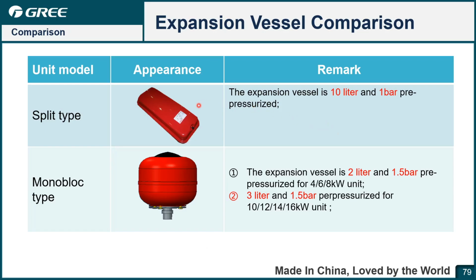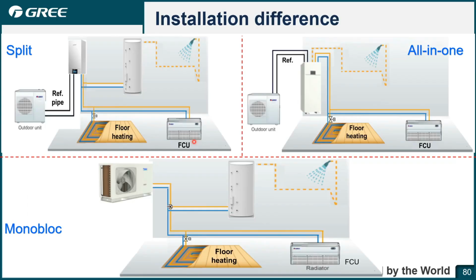And here is the expansion vessel comparison. So split and all-in-one use this expansion vessel, which is 10 liter and 1 bar preset pressure. For the monoblock, the 4, 6, and 8 kilowatt units are 2 liter and 1.5 bar preset pressure. And from 10 kilowatts to 16 kilowatts is 3 liter and 1.5 bar preset pressure. So actually, that's another difference between the split, all-in-one and monoblock.